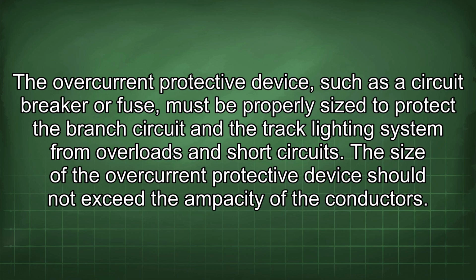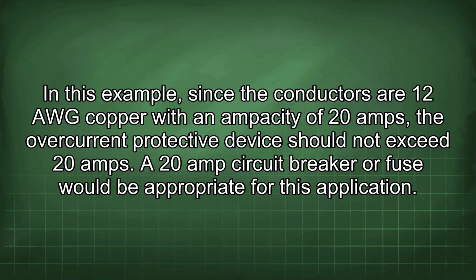The size of the overcurrent protective device should not exceed the ampacity of the conductors. In this example, since the conductors are 12 AWG copper with an ampacity of 20 amps, the overcurrent protective device should not exceed 20 amps. A 20 amp circuit breaker or fuse would be appropriate for this application.